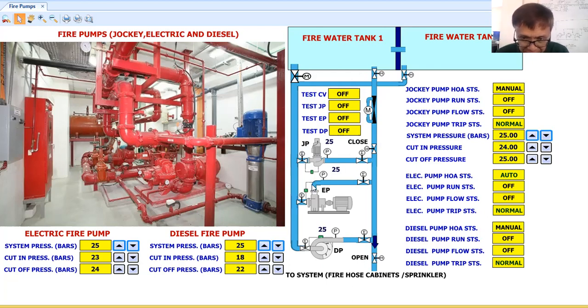Now, for the testing of the mechanical electrical pump, since these electrical pumps are big and powerful, they can deliver a really big amount of water. Especially in the Middle East, you cannot waste water, because water is very important in that part of the world. So what we have here is the isolation valve or gate valve. Then I also have an isolation valve or gate valve in my main riser going to the building, or to the sprinkler and fire hose cabinets.